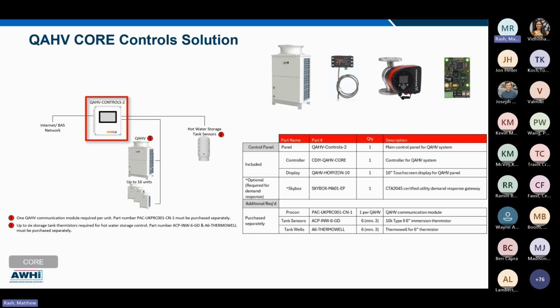Again, that includes the meters, so you get that COP functionality built in if you include the supervisory panel with the solution. That would have to be a custom quote solution or custom field provided with the core. So those are the main differentiators. And then obviously with the skid, you've got everything pre-piped, and that's really the lowest complexity in terms of install, but also the highest cost.